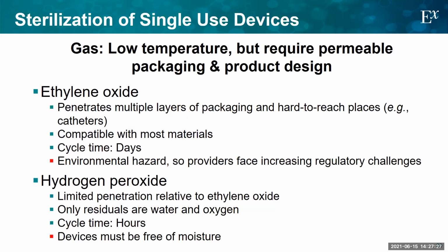Okay, we're going to shift gears here a little bit just to talk about single-use devices. So if we have a single-use device, then obviously it has to be delivered sterile. And there's a couple of ways to think about sterilization. First would be with a gas. And the advantage of gas sterilization is that it's very low temperature, but it requires packaging and a design of a product that allows it to be permeable to the gas.